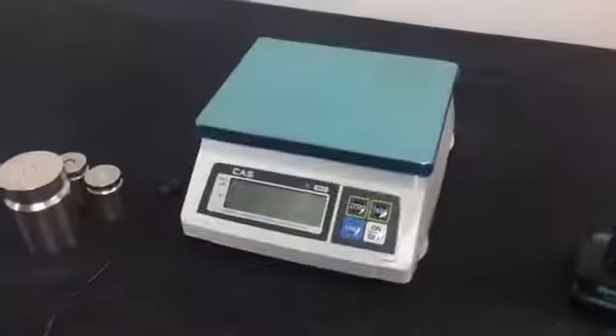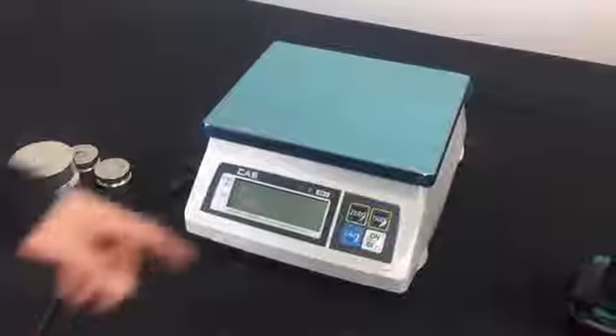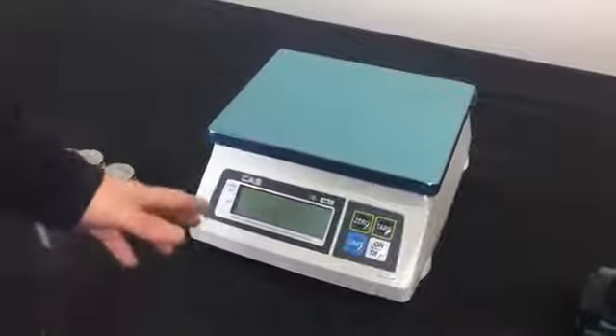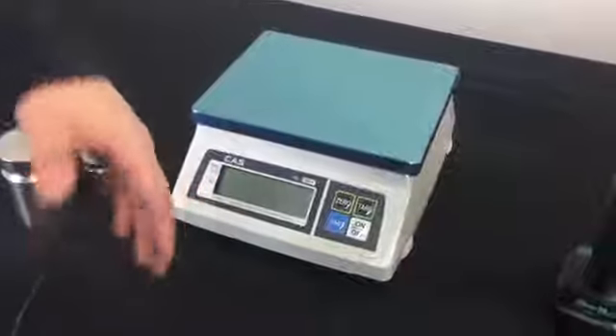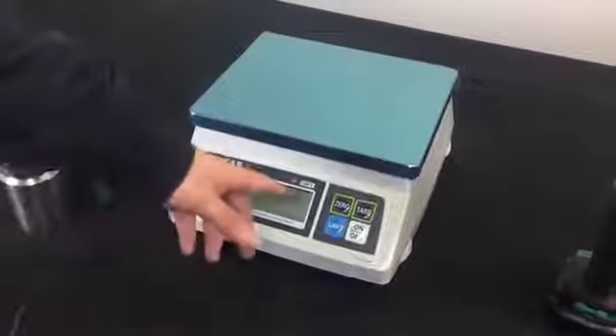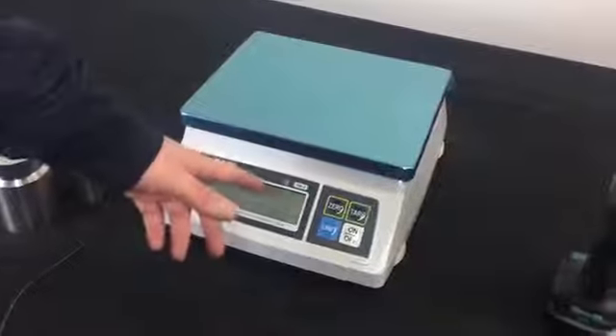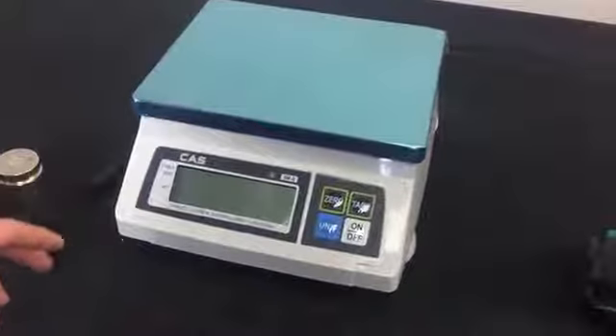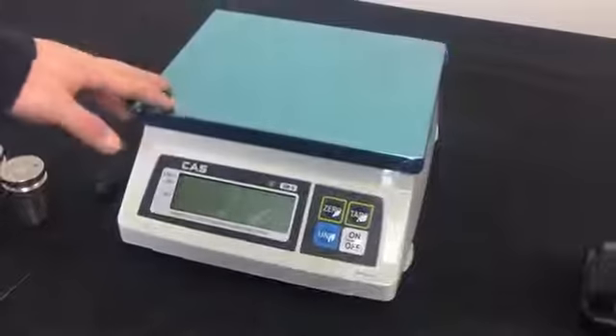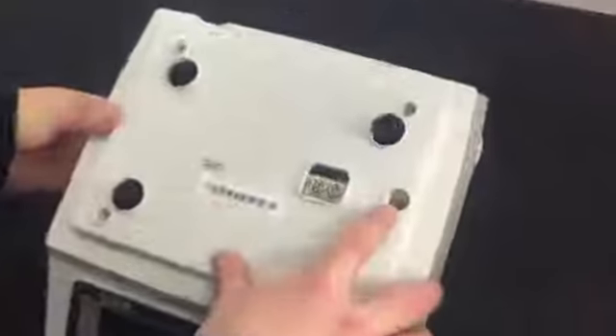This video today is to show you the calibration procedure for the SW series. I'm going to be using an SW5. When you're calibrating, make sure that you do look for the proper capacity of your scale and know what actual scale you're working with. Now, the first thing we're going to want to do is remove the platter on the top of the scale just so we can locate inside here in this port.